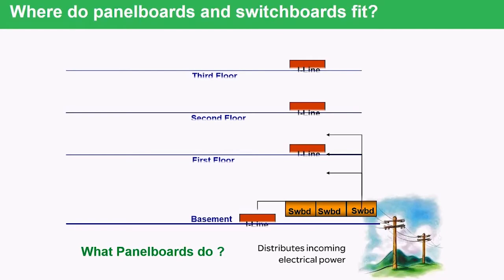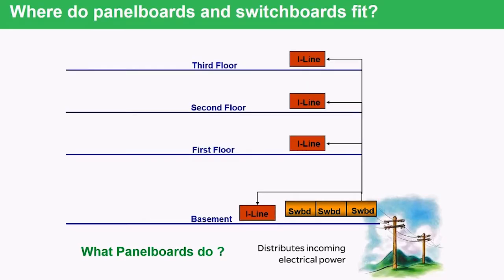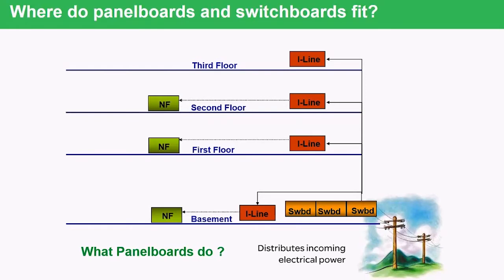From this switchboard, we will break the power down into smaller chunks. It could be fed to an I-line panel board in the same room as the switchboard, or they could be on different floors of the building. These I-line panel boards will break the amperage down into smaller pieces, feeding panel boards. In this particular picture, we're looking at a 480-volt switchboard feeding I-line breakers and I-line panel boards that are feeding NF panel boards.